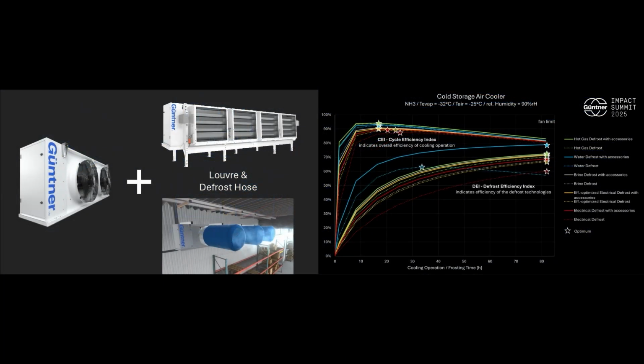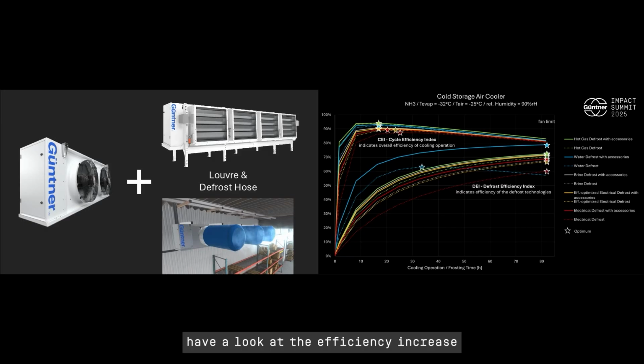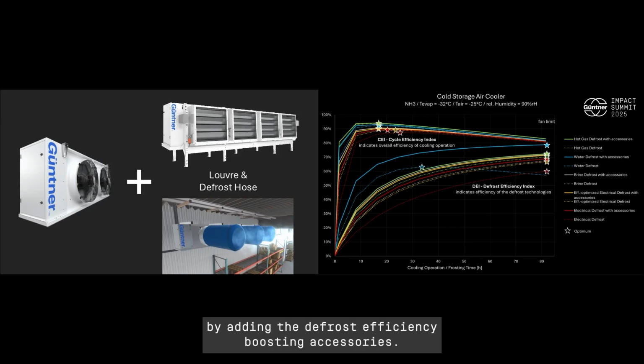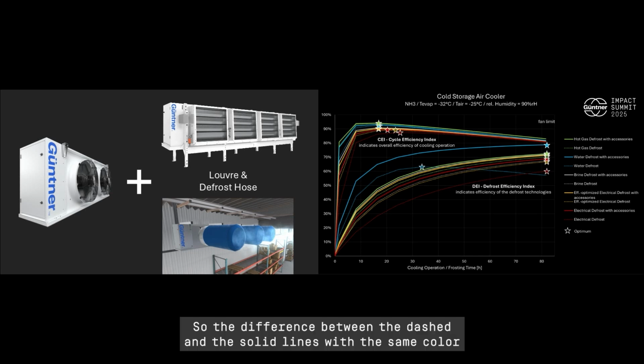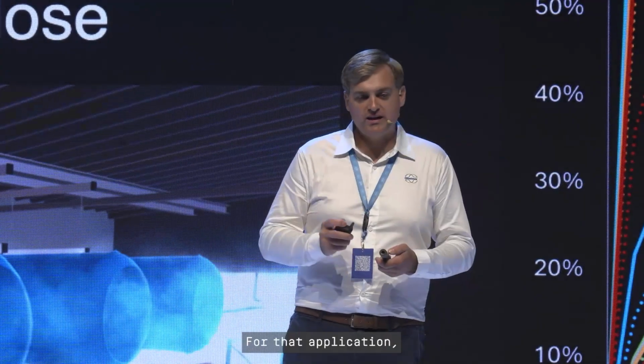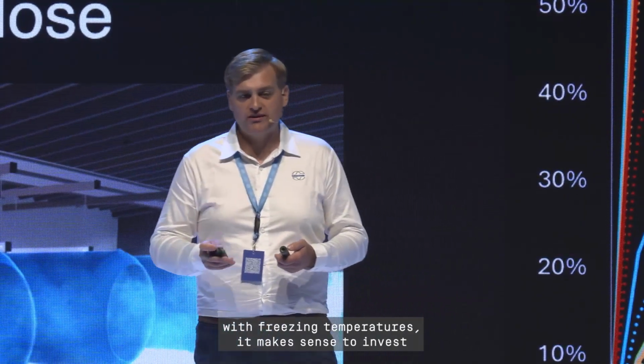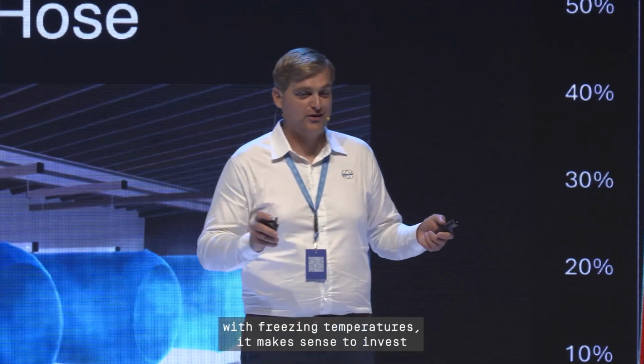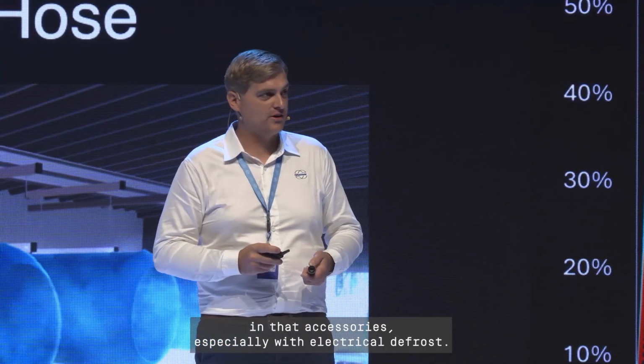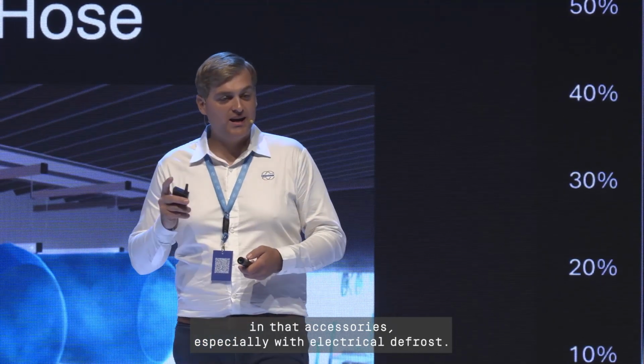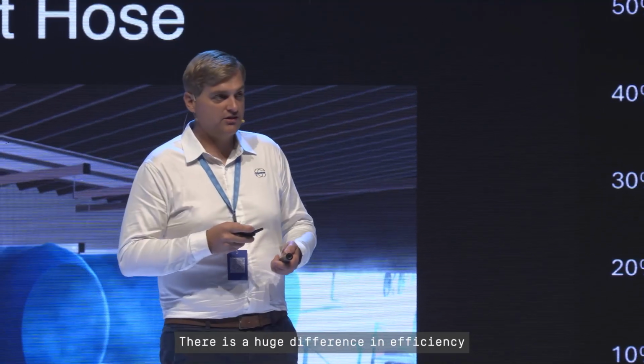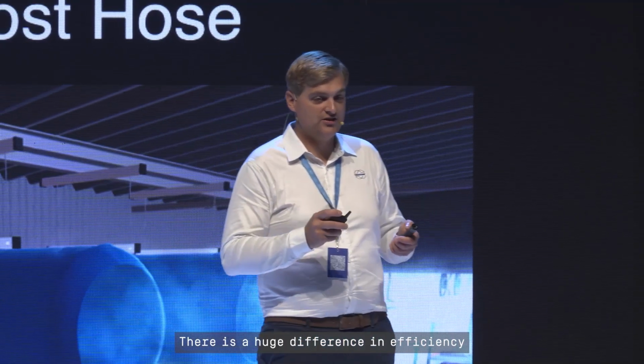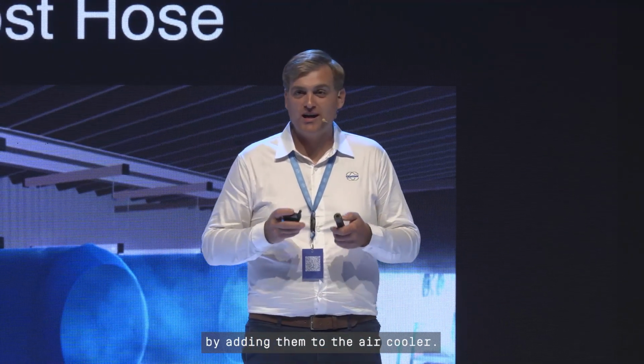First, have a look at the efficiency increase by adding the defrost efficiency boosting accessories. So the difference between the dashed and the solid lines with the same color. For that application, with freezing temperatures, it makes sense to invest in that accessories. Especially with electrical defrost, there is a huge difference in efficiency by adding them to the air cooler.